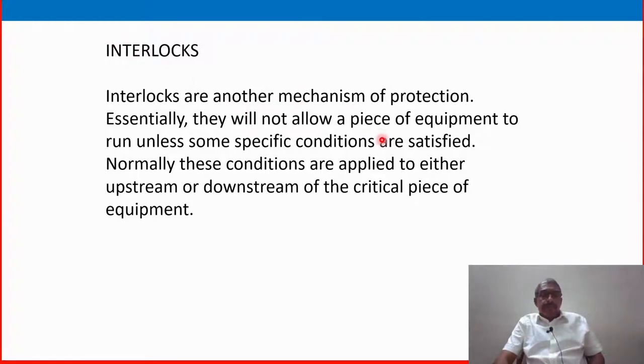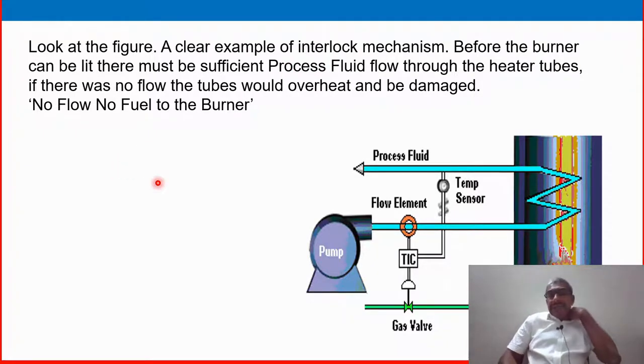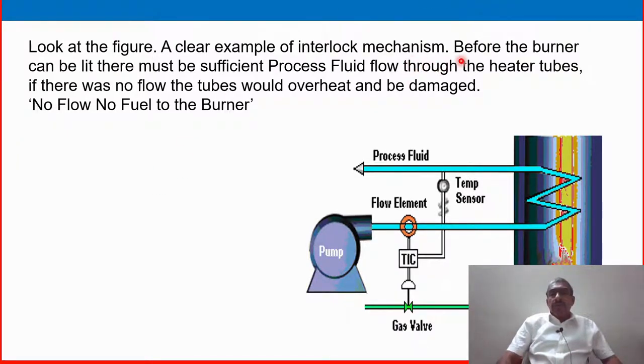Next is interlocks. Interlocks are another mechanism of protection. They will not allow a piece of equipment to run unless some specific conditions are satisfied. Normally, these conditions are applied to either upstream or downstream of the critical piece of equipment. A clear example of the interlock mechanism: before the burner can be lit, there must be sufficient process fluid flow through the heater tubes. If there was no flow, the tubes would overheat and be damaged.